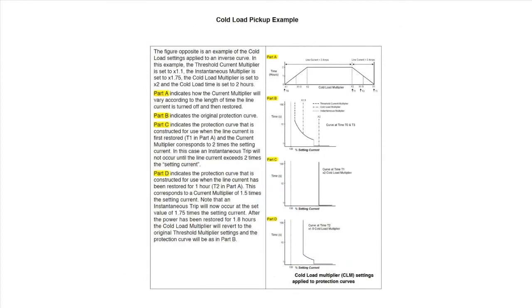The purpose of the cold load pickup feature is to compensate for the loss of diversity automatically, so the increased load will not cause overcurrent protection to operate. It works by measuring the time that supply is lost, and then temporarily raising the trip current for a time according to the time supply was lost. The increase in trip current is determined by the cold load multiplier that is set by the user. The user specifies a multiplier and a time. The ADVC detects when load current is 0 and starts a timer called the operational cold load time.